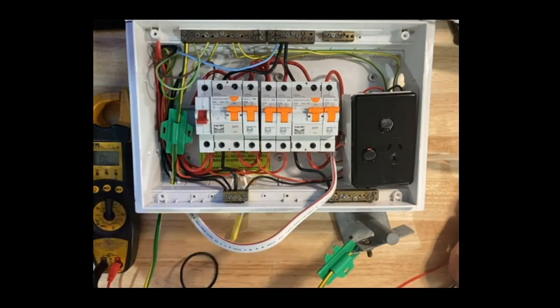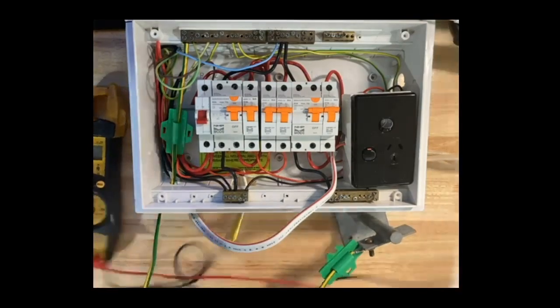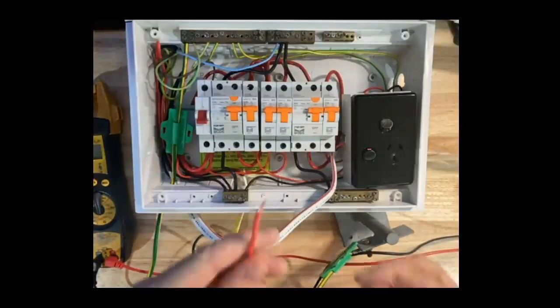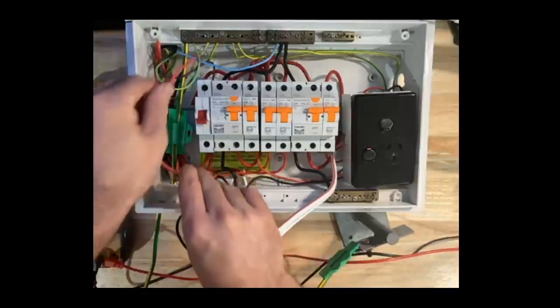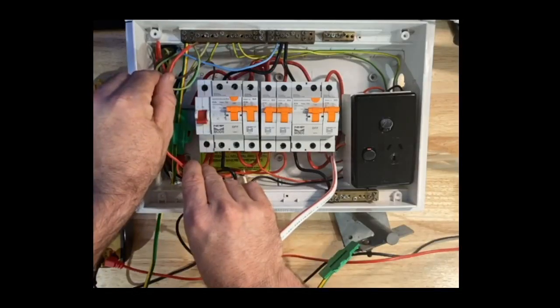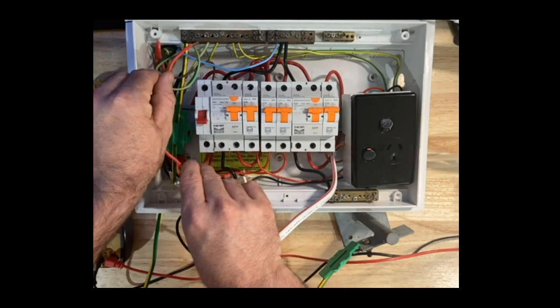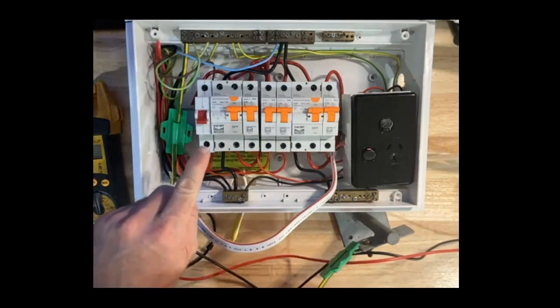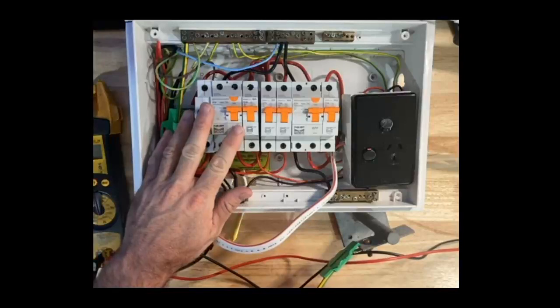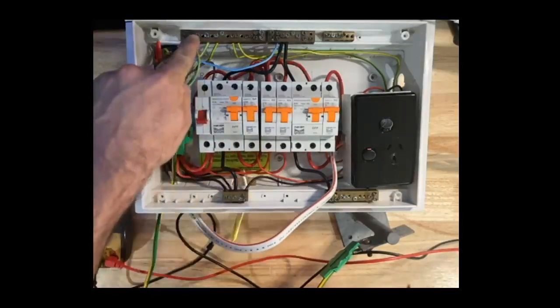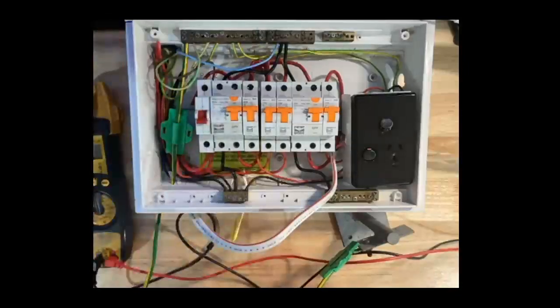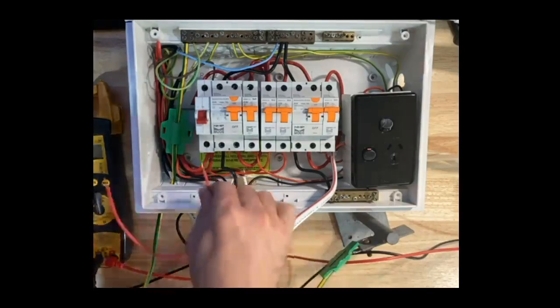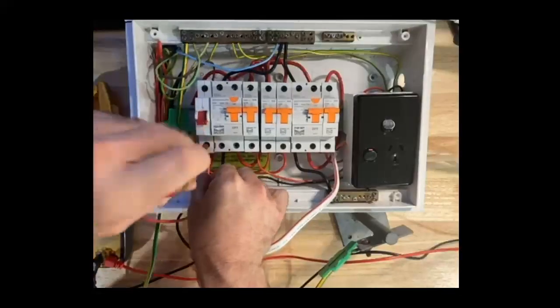So there is a methodology that is described in the standard that allows us to do this, and that is to connect my phase conductor to the earth busbar. Now, it's important to note here that I will only do this on a switchboard that is not live, right? That makes sense, doesn't it? Because if I start connecting my phase to my earth on a live switchboard, terrible things are going to happen. So I can assure you that this is not live. If we were doing a new installation, I would be doing this before the mains is connected. So before the mains is connected, I'm going to run a wire from my main switch.